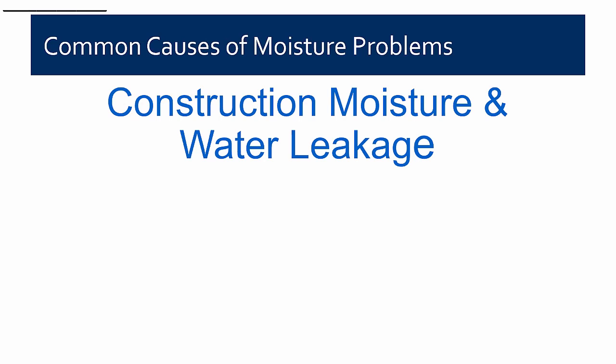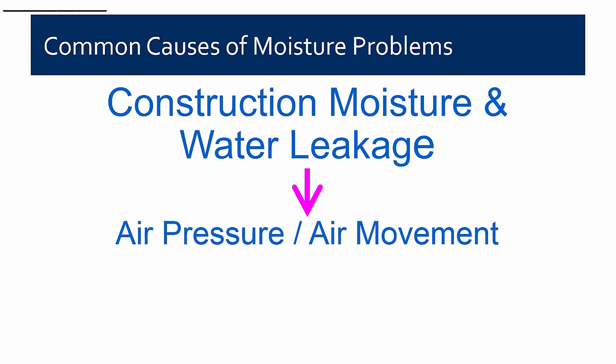When looking at moisture problems in a building, always start with the most obvious and rule those out first. In most cases, water leakage is often the cause — a leaky pipe, roof leakage, wall leakage, or construction moisture, especially in newly built buildings where water may have been trapped when insulation and membrane were installed. Construction moisture is probably still the number one cause. But the second cause is air pressure and air movement. If you haven't ruled out water leakage and construction moisture and it's a condensation-related problem, most likely it's related to air pressure differential and associated air movement.